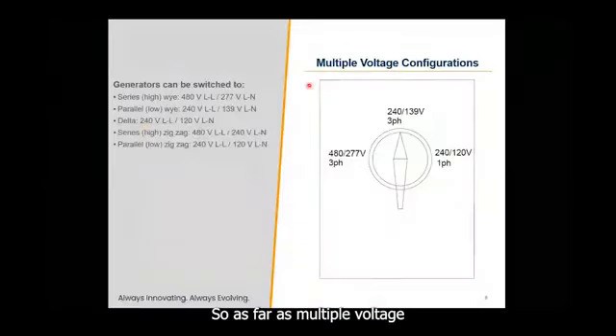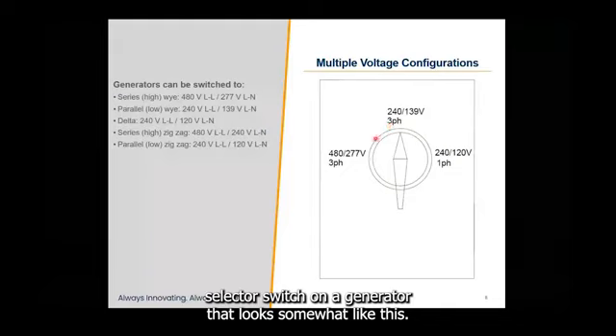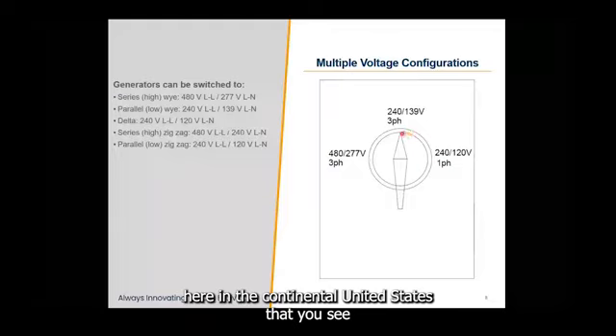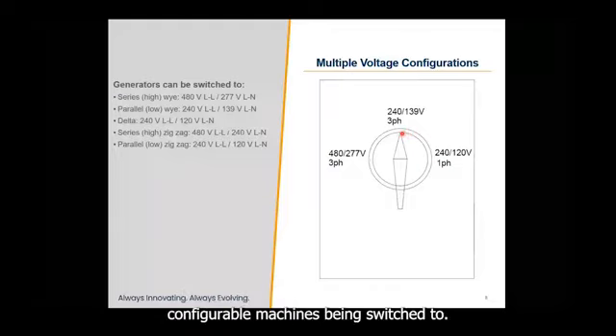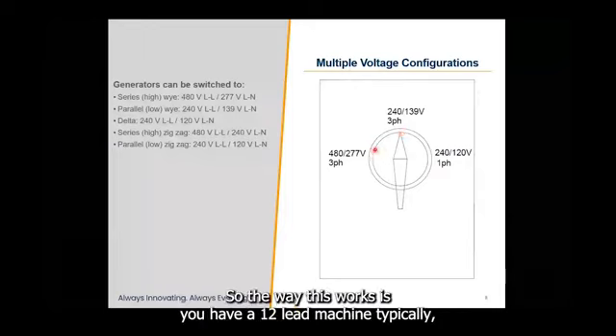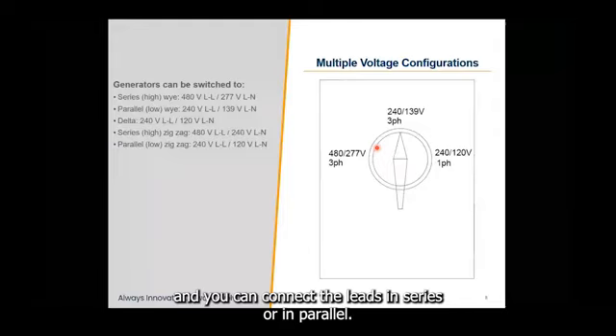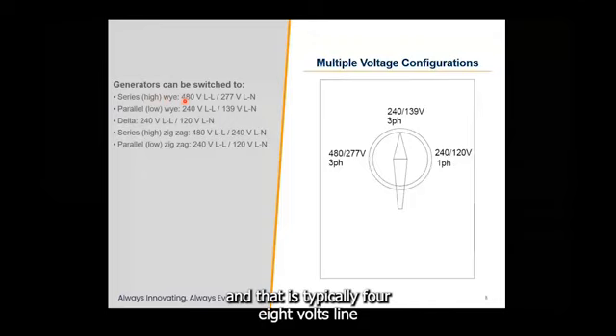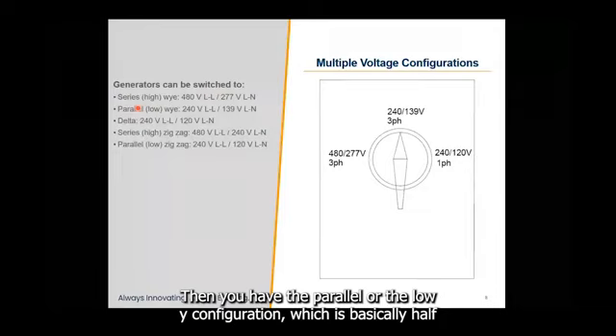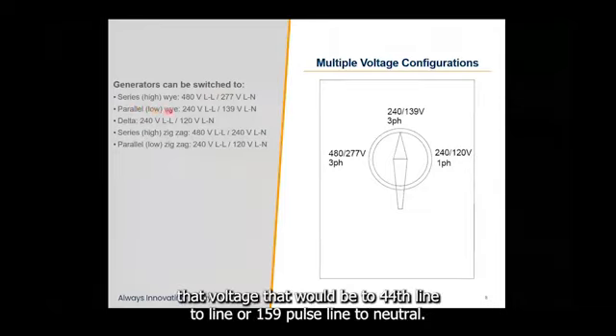So as far as multiple voltage configurations go, you may have seen a selector switch on a generator that looks somewhat like this. This is just one example showing some typical voltages here in the continental United States that you will see configurable machines being switched to. The way this works is you have a 12 lead machine typically, and you can connect the leads in series or in parallel. When the leads are connected in series, this is called the series or high Y configuration. And that is typically 480 volts line to line, 277 volts line to neutral. Then you have the parallel or the low Y configuration, which is basically half that voltage. That would be 240 volts line to line or 139 volts line to neutral.